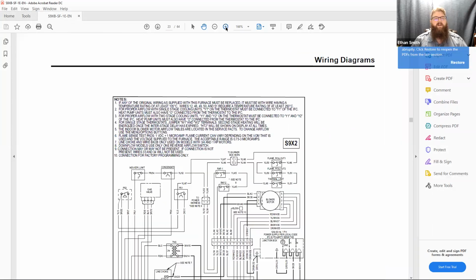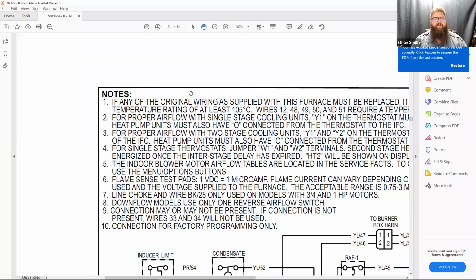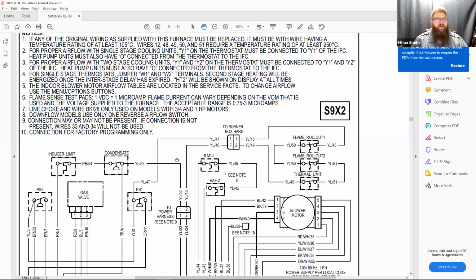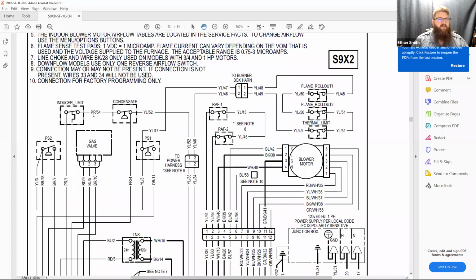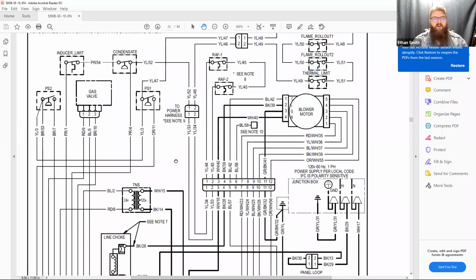Okay, so if we blow this up here, you'll notice we've got all our notes up at the top. Back off one here. But we've got all of our wires here, and you'll notice that they're marked PR54. So this is wire purple 54. And you'll notice it also tells you it goes between the inducer limit and the condensate limit. So you can go to the end of that wire at the inducer limit, and it will be labeled 54, and it's purple. And you can go to the condensate switch and make sure that that wire lands at the right point on the condensate switch. Make sure that you haven't gotten PR4 over here and PR54 over here, because that's going to create problems. Okay, so it makes it really easy to trace wires through equipment with some of these designators once you know what they are.